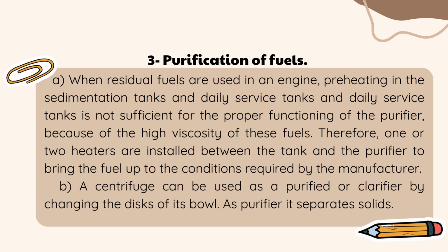Therefore, 1 or 2 heaters are installed between the tank and the purifier to bring the fuel up to the conditions required by the manufacturer. B. A centrifuge can be used as a purifier or clarifier by changing the discs of its bowl. As purifier, it separates solids.